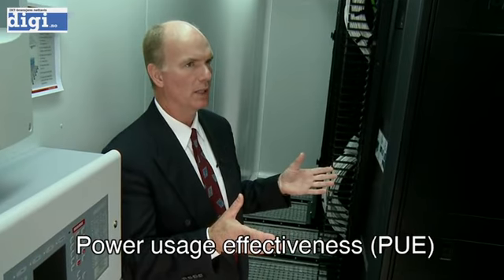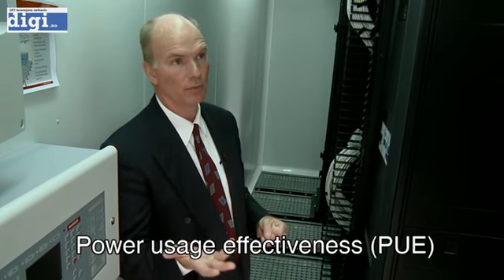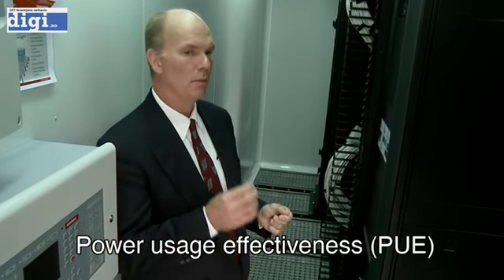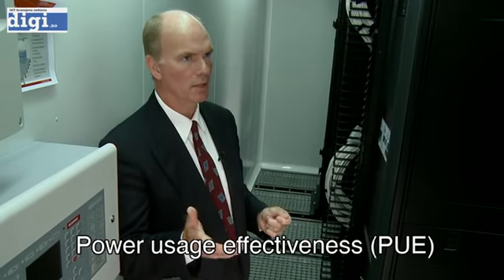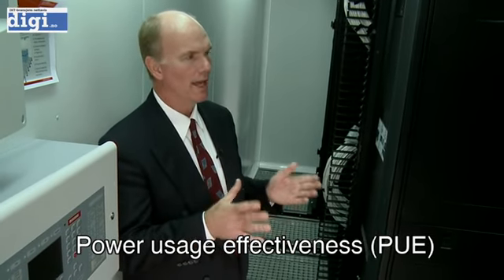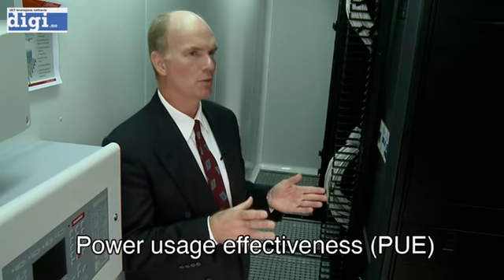The typical design has a PUE of about 1.3. If you compare that to a regular data center today, most of the data centers we see — and we do studies on many, many data centers — they average a PUE of about 2.5 to 2.7. So this being 1.3 is much, much more efficient than what you'll find.